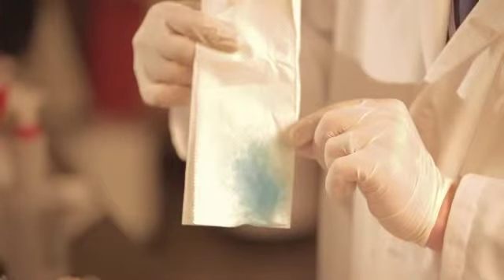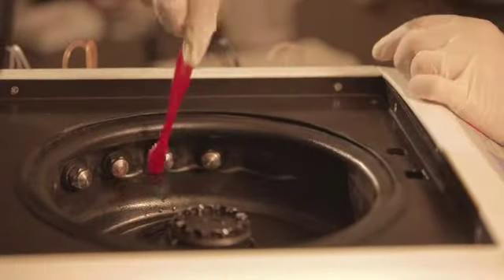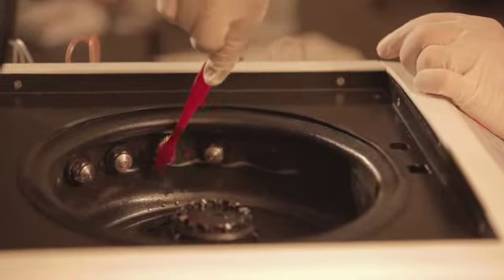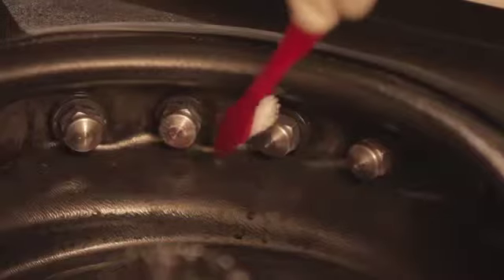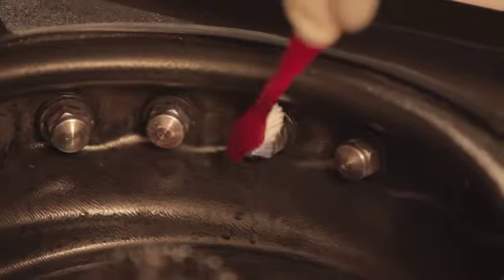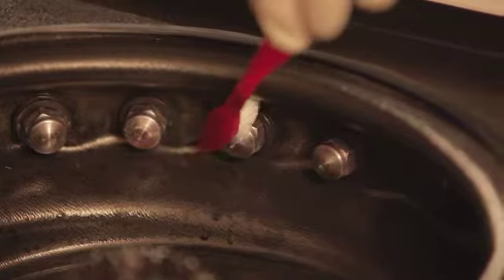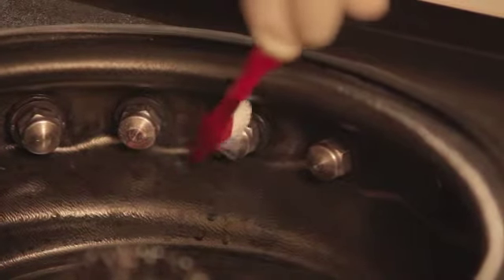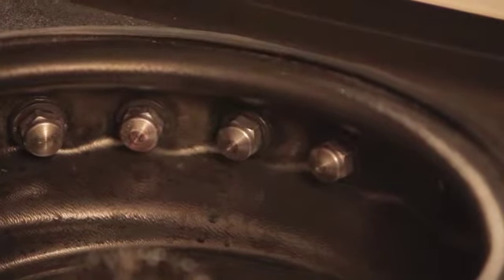If either the spray pattern or volume collected is not as it should be, then the nozzle needs to be cleaned. An easy way to quickly clean the nozzle is by using the cleaning brush provided in the nozzle maintenance kit. Use this brush by forcing the bristles into the orifice of the nozzle. This cleans the nozzle quite well, and by doing this will divert the need to disassemble and clean the nozzle.